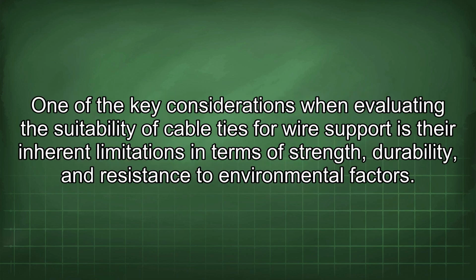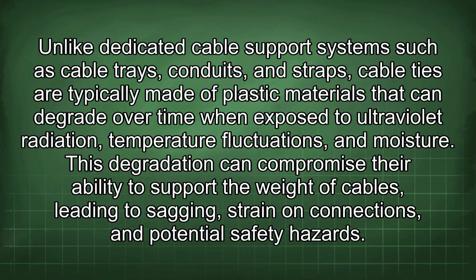One of the key considerations when evaluating the suitability of cable ties for wire support is their inherent limitations in terms of strength, durability, and resistance to environmental factors. Unlike dedicated cable support systems such as cable trays, conduits, and straps, cable ties are typically made of plastic materials that can degrade over time when exposed to ultraviolet radiation, temperature fluctuations, and moisture. This degradation can compromise their ability to support the weight of cables, leading to sagging, strain on connections, and potential safety hazards.